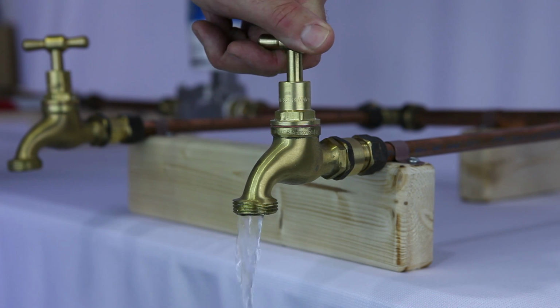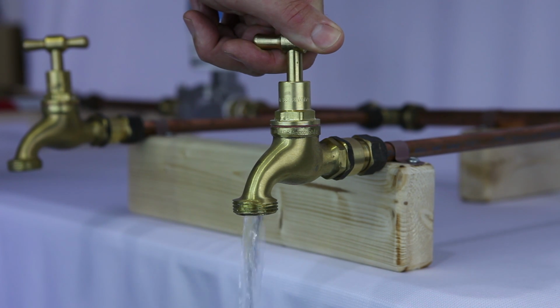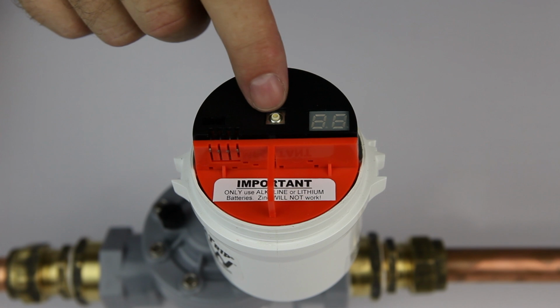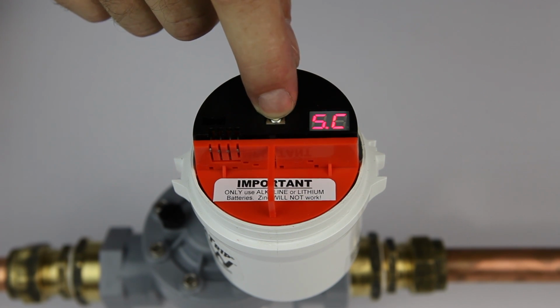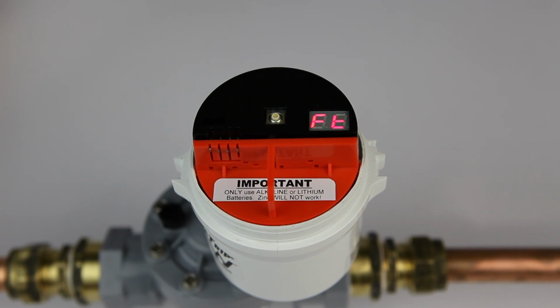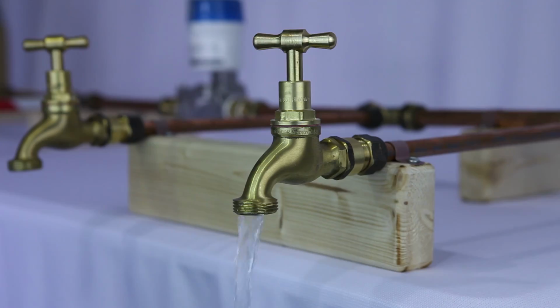Control panel radio range test. The valve must be tripped for the radio range test to be done. So, turn on the tap, then go to the control unit, hold the button down until you see FT for fast test and release. Shortly after you release the button, the water will turn off. You can now conduct the range test.